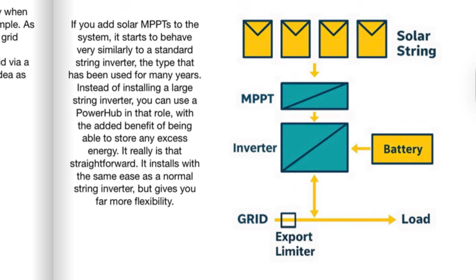It can export if you want, or it can store the energy into the battery, so you've got a choice and you can program it. Generally it functions exactly the same as a standard string inverter - no difference, it wires the same. So if it's a 50 kilowatt or 100 kilowatt inverter, just imagine it's a 50 or 100 kilowatt string inverter, but it gives you the benefit of battery.